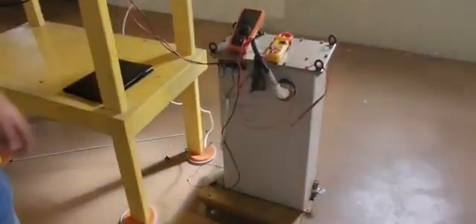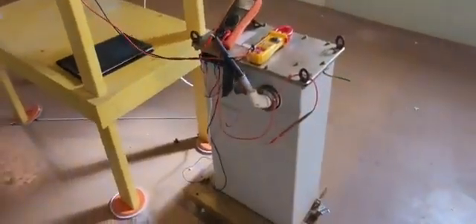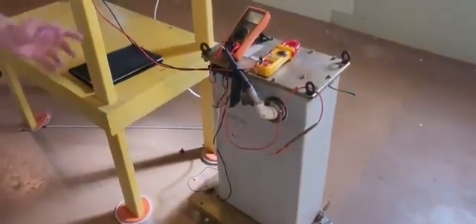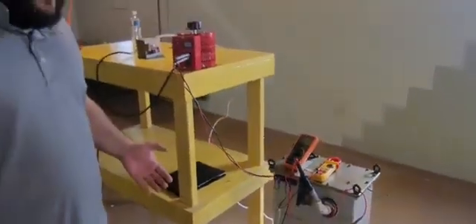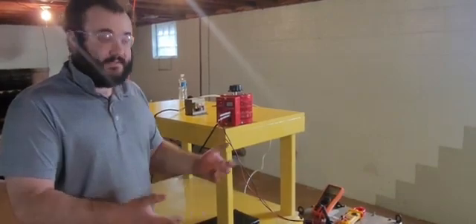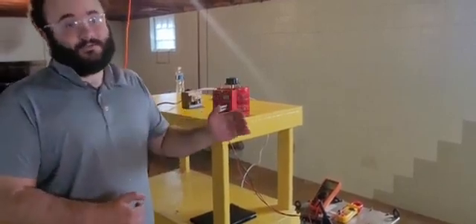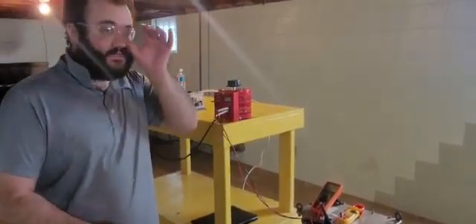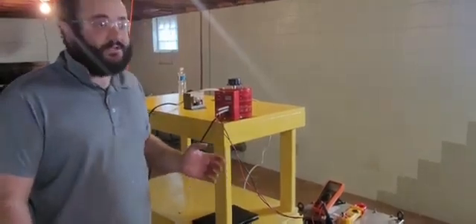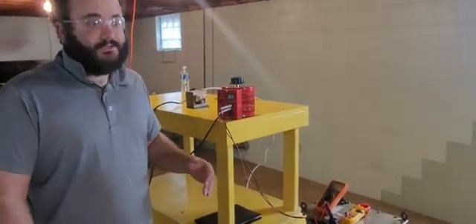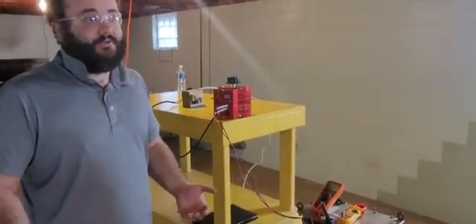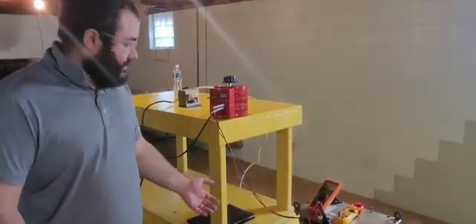And a little thing about X-ray generators is they are used to power the X-ray machines you find in your hospital. They use extremely high voltage in what's called an X-ray tube, which is an old type of vacuum tube that's still used today in X-ray machines. They're very large and they operate anywhere between 50 and even up to 400 kilovolts, 400,000 volts. They do this so they can generate the X-rays needed to go through your body and take the image of your bones or whatever doctors are trying to look at.